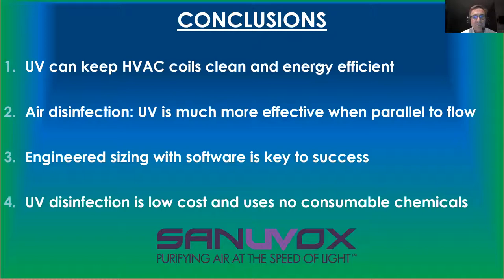Not sure, Dean, I understand the question. As far as upstream and downstream goes, installation, does it matter? Yes, it does. It does matter. Actually, if you're putting in upstream, you're dealing with air that is not as cold, and you're preventing the fouling from droplets hitting the lamps, from condensation hitting the lamps. But you need to size it with enough power to go through the coil and clean the opposite side.